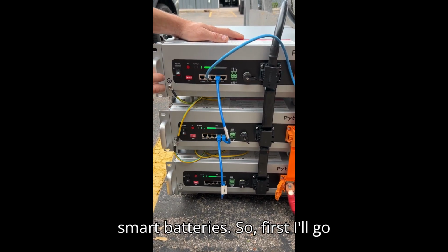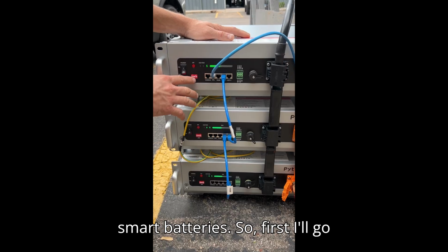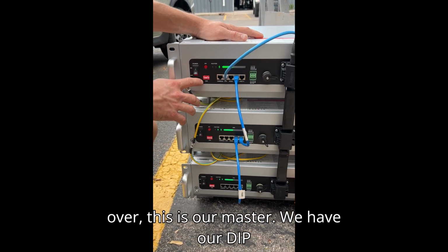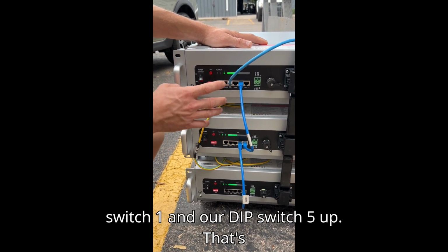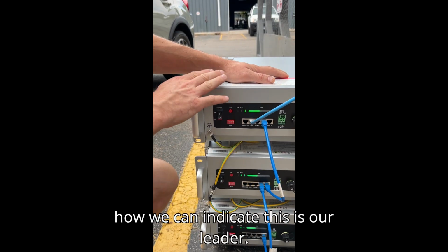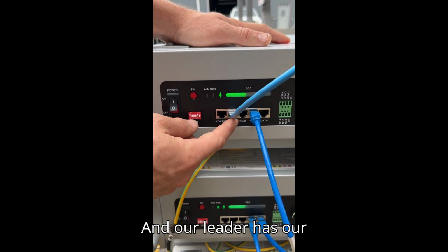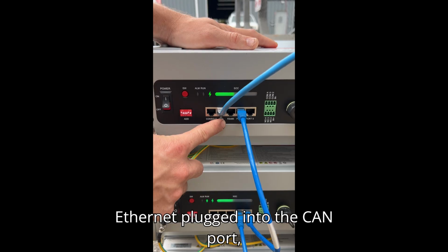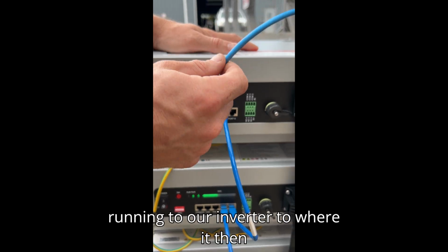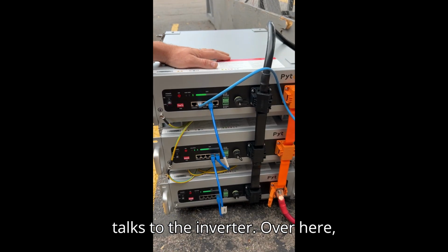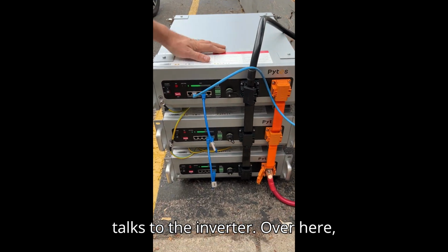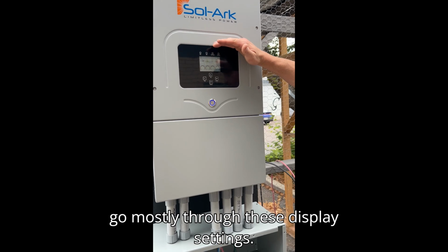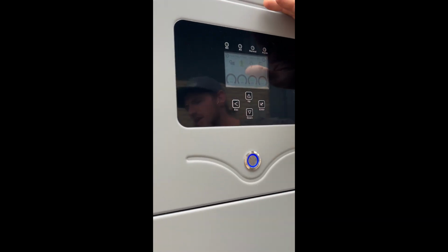They're smart batteries. This is our master. We have dip switch 1 and dip switch 5 up, that's how we indicate this is our leader. Our leader has our Ethernet plugged into the CAN port, running to our inverter, where it then talks to the inverter. Now we'll move on to the Sol-Ark and go mostly through these display settings.